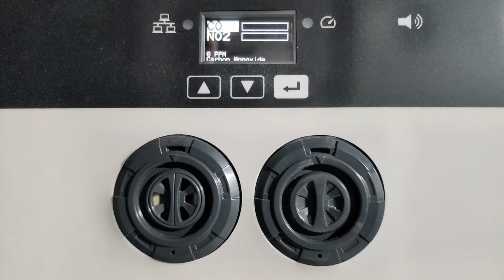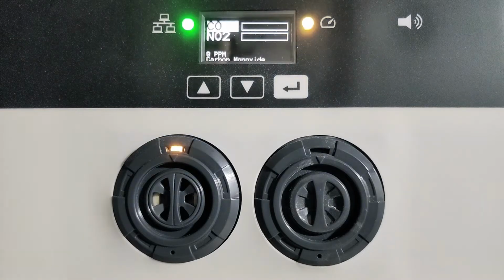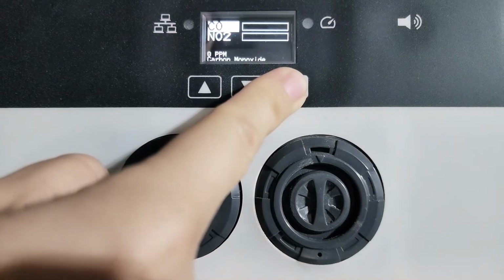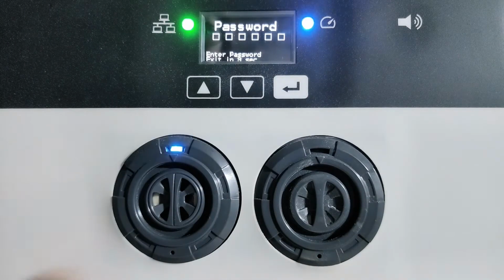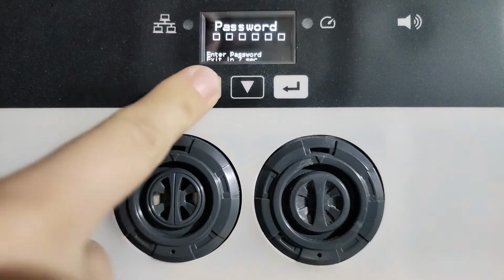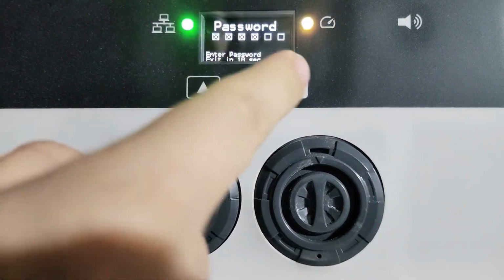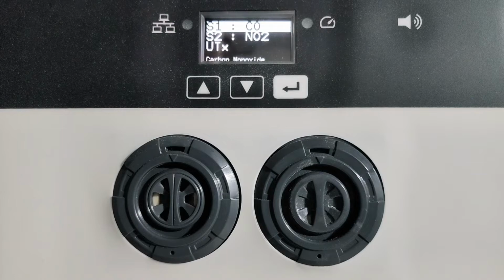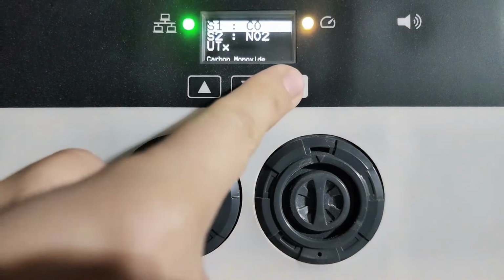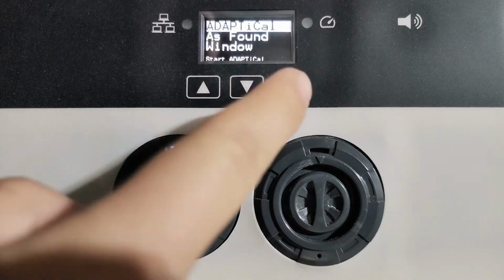When a unit is due for calibration, the sensor module LED will blink light blue and yellow as opposed to its usual green. To start calibration, long press on the Enter button, then enter the password, which is up, down, enter, enter. You'll then be asked to select the sensor that you want to calibrate. In this case, we're calibrating the carbon monoxide sensor, or CO. So you hit enter, and then you select AdaptiCal.